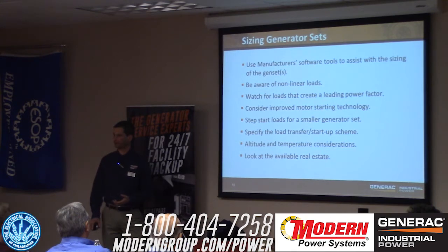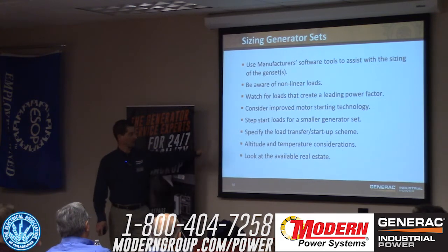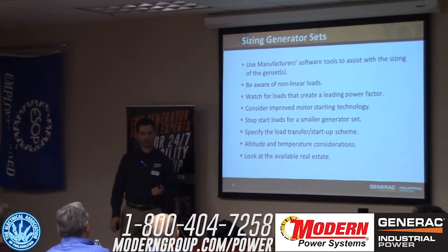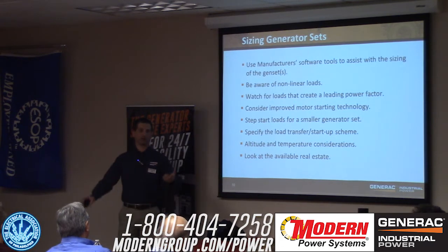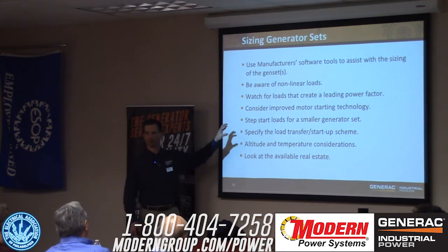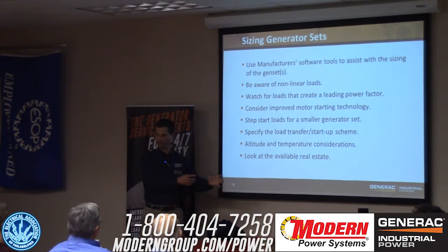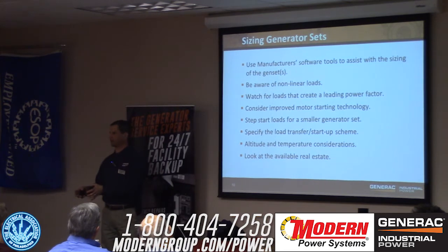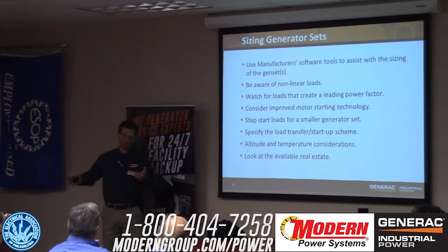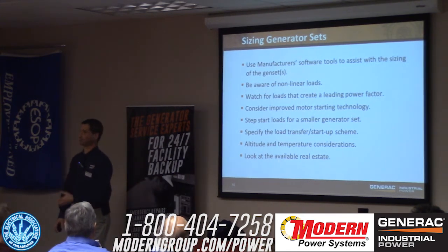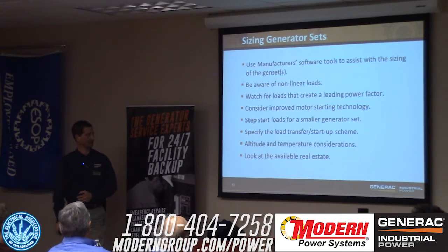Maybe put a VFD in there. Then you can talk to Chad too, get some credits too. Okay? That's going to significantly reduce that starting current requirement for that motor. You might be able to save the expense of upsizing an alternator. And your end user saves some money a little bit too. So kind of a win-win. It comes down to, where am I going to throw the money? Am I going to throw the money at the alternator on the generator set? Or am I going to spend a little bit of money on a VFD? Customer is going to spend it. They've got to start that motor one way or another. Maybe add a little bit of value, every day when that motor starts, anytime.